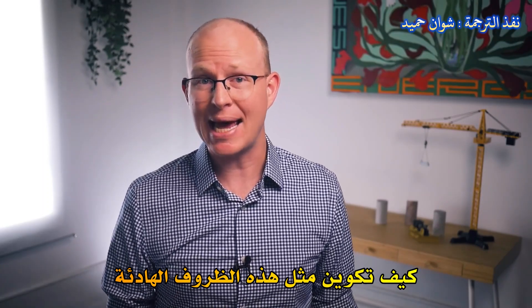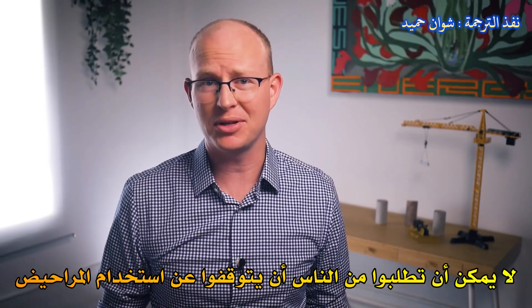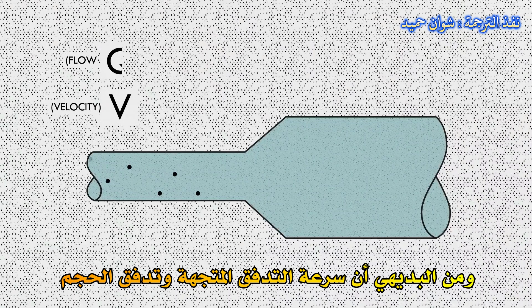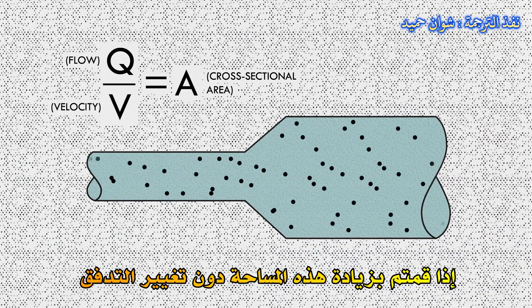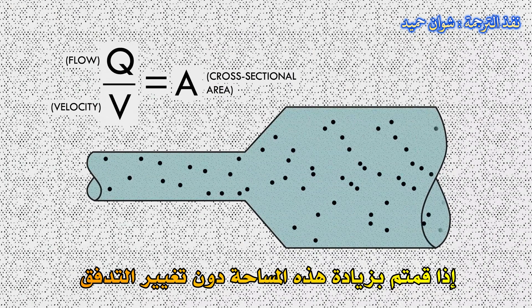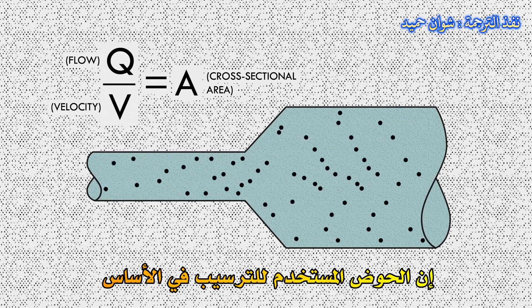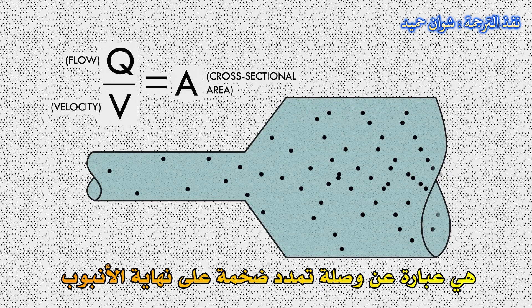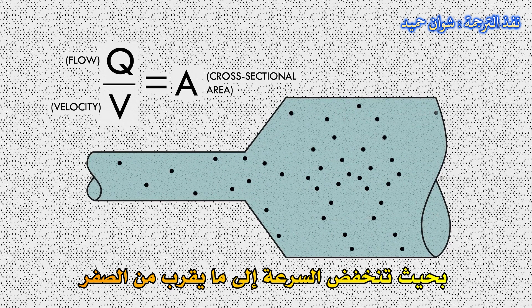How do you create such placid conditions from a constant stream of wastewater? You can't tell people to stop flushing or showering to slow down the flow. Velocity and volumetric flow are related by a single parameter: the cross-sectional area. If you increase this area without changing the flow, the velocity goes down as a result. Basins used for sedimentation are essentially just enormous expansion fittings on the end of the pipe, dramatically increasing the area of flow so the velocity falls to nearly zero.